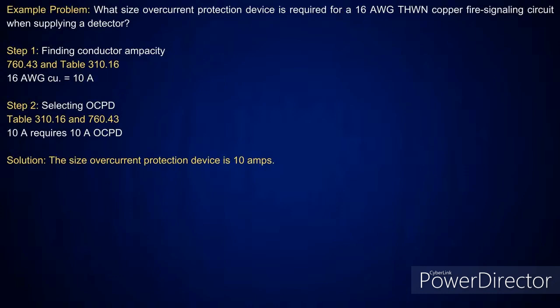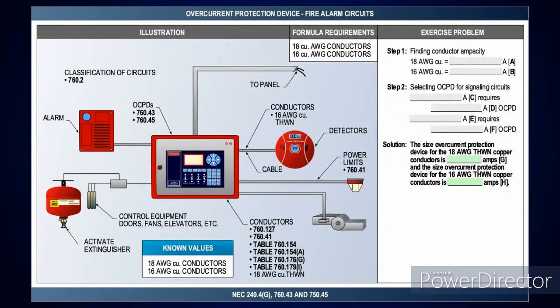This is awesome. Now we're going to look at a fire signaling circuit. This is actually given to you when you go over and look at 760.43, but we're just sort of proving a couple of things here. When you look at table 310.16, you pick up the 75 degrees C column, it tells you number 16 is good for what? Number 10. Therefore, you look at 760.43, it matches up. You need a 10 amp overcurrent protection device. Pretty simple. And then we did a setup here.